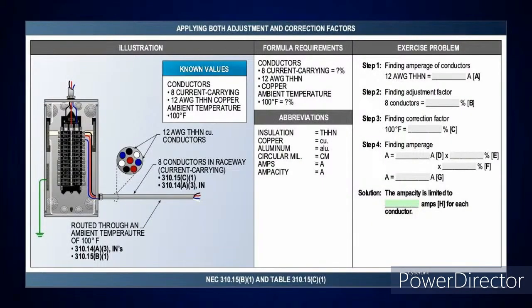And you've got another exercise: eight current-carrying number 12 THHN conductors routed through an ambient of 100°F. Use the 90°C column. Get your adjustment factor for eight conductors from Table 310.15C1, and your correction factor for 100°F from Table 310.15B1. Take the amperage of the conductor, multiply it by both percentages, and that's what your conductor is limited to. Pretty simple.